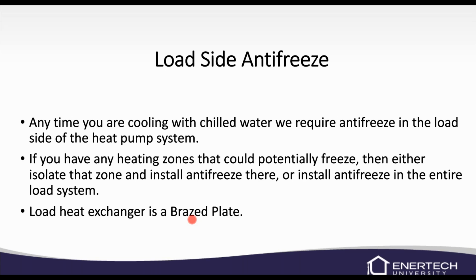Load and source braze plates, they don't handle freezing very well. If you freeze it once, you might get lucky. You freeze it twice, I guarantee you won't. It'll bulge, it'll separate, it'll allow the water to enter the refrigerant circuit.